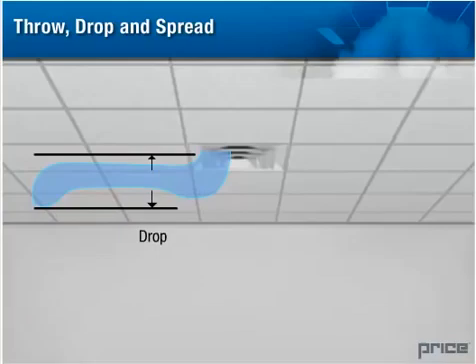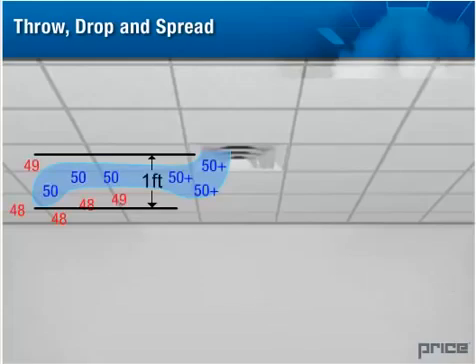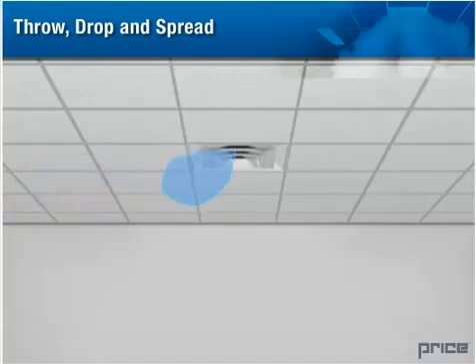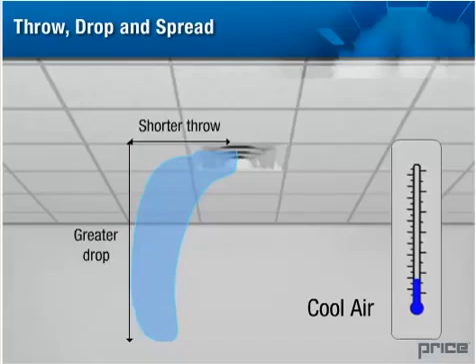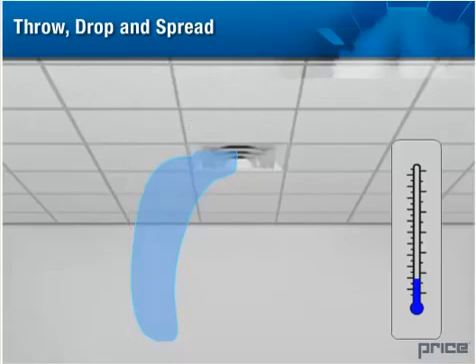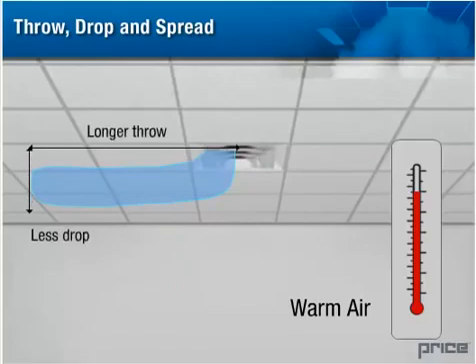Drop is the vertical distance from the diffuser to the bottom of the air jet. When we determine the drop, we also measure this distance for a specific air velocity. For example, the drop of this SCD is one foot at a terminal velocity of fifty feet per minute, meaning the air velocity at a point one foot below the diffuser is fifty feet per minute. The temperature of the supply air affects both throw and drop: cool air is more dense and tends to fall away from the ceiling, resulting in shorter throw distances and greater drop.